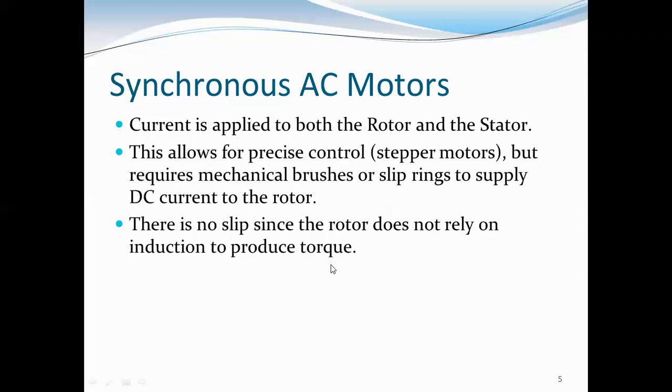Here, the synchronous motors are used with the slip rings or the brushes. Why? Because the DC supply is moving towards the rotor circuit, and an AC supply is provided for the stator. A three-phase rotating magnetic field is produced, the same as in the induction motor. But what about the synchronous rotor? The rotor is provided with the DC supply. Therefore, the slip rings or the brushes are a must. Therefore, here the synchronous motor is called a double excited machine.